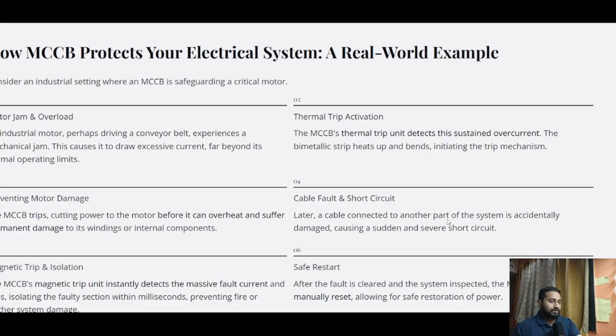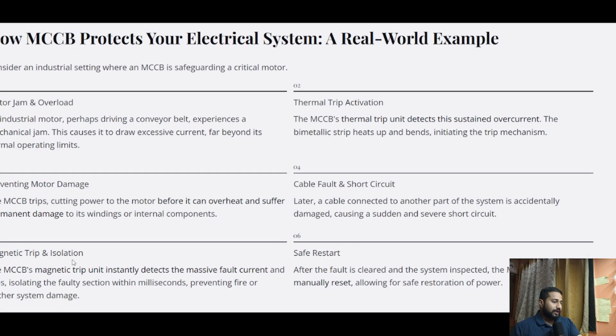Later, a cable connected to another part of the system is accidentally damaged, causing a sudden and severe short circuit. The magnetic trip and isolation action comes in, wherein the MCCB's magnetic trip unit instantly detects the massive fault current and trips, isolating the faulty section within milliseconds, preventing fire or further system damage. And it also offers a safe restart. After the fault is cleared and the system is inspected, the MCCB can be manually reset, allowing for safe restoration of power. So we have seen a real world example wherein the motor was jammed and overloaded.